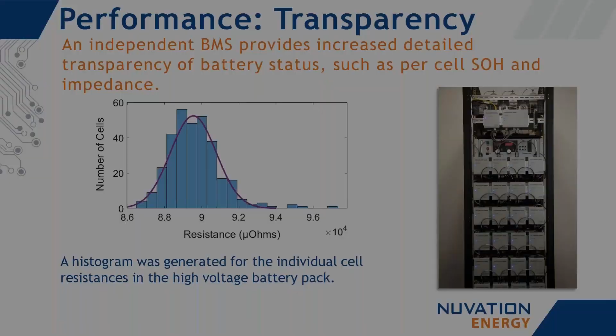This is an example of our high voltage stack, one of our test systems in Waterloo. We ran our cell impedance algorithm on it, and it generated this histogram showing each individual cell's impedance. Interestingly, there were a few cells with statistically higher impedance.